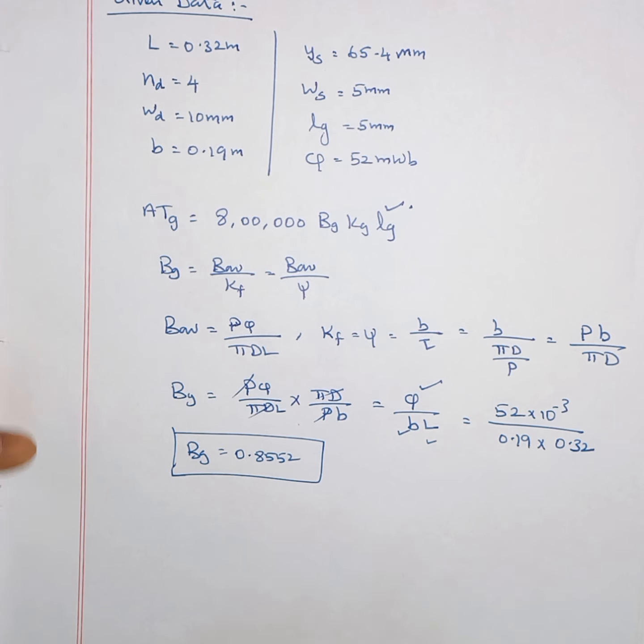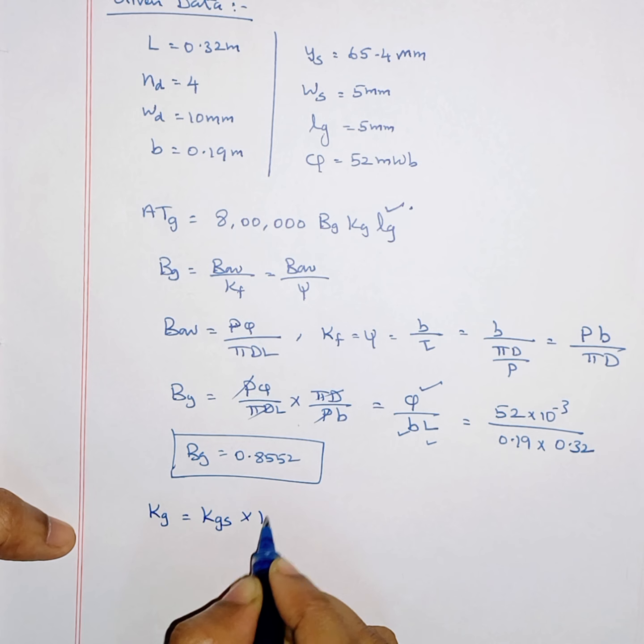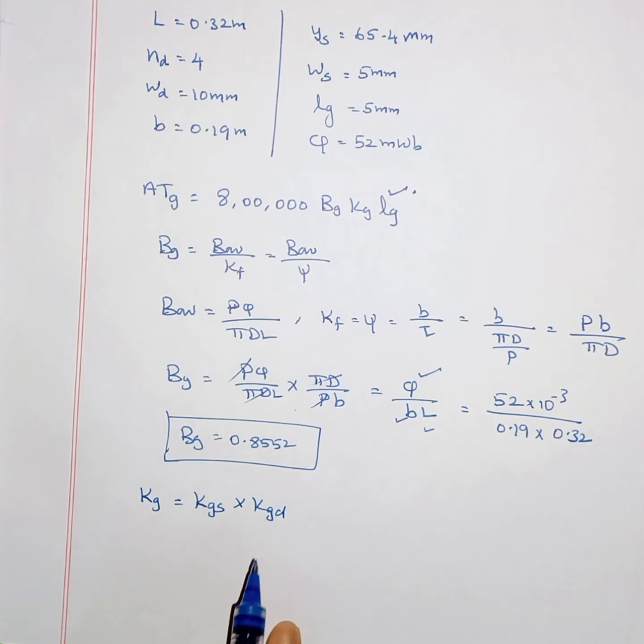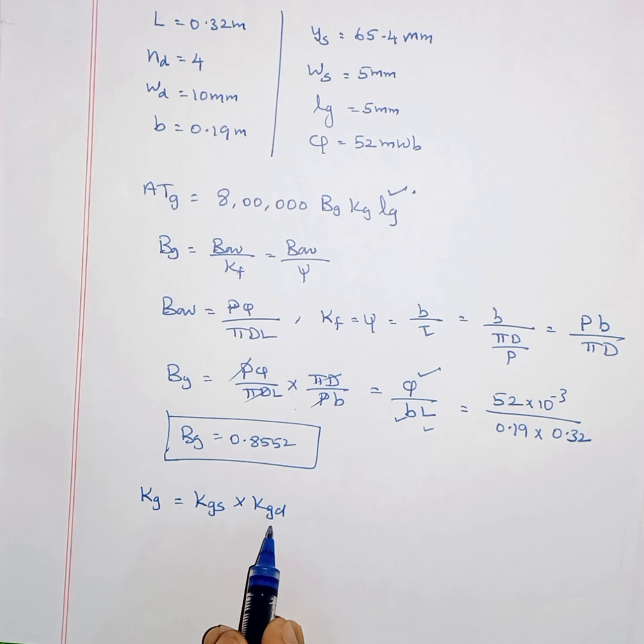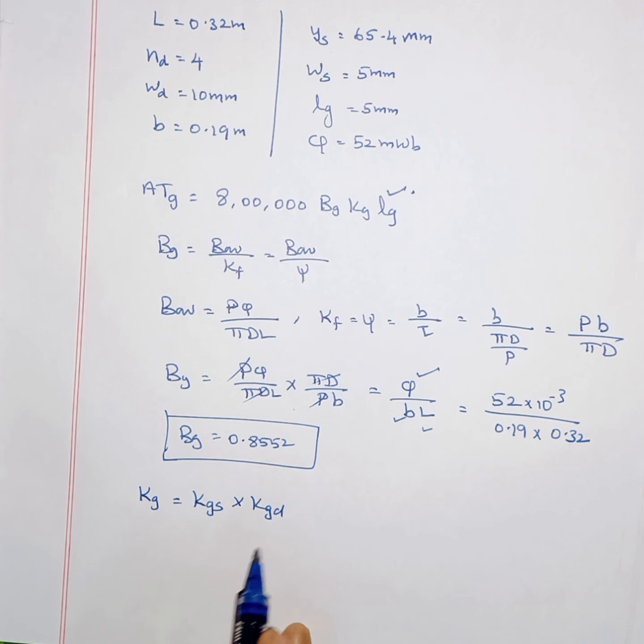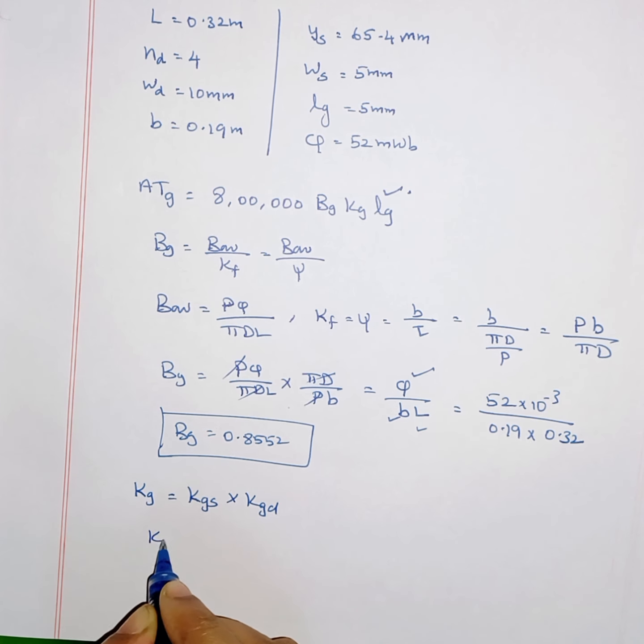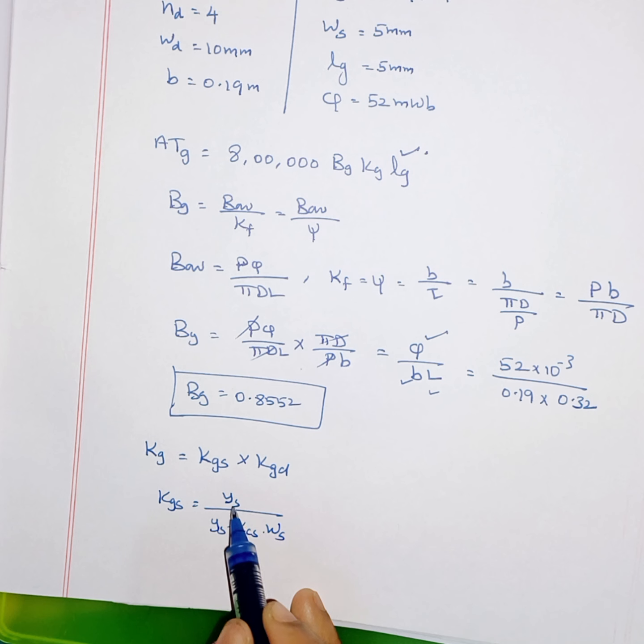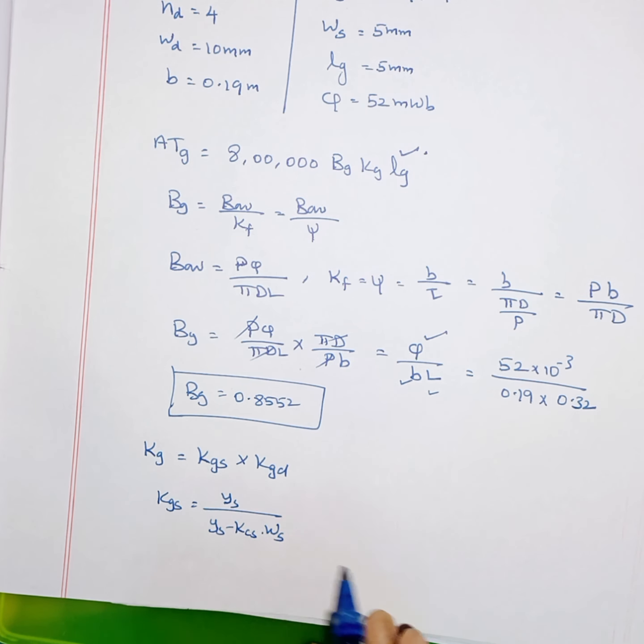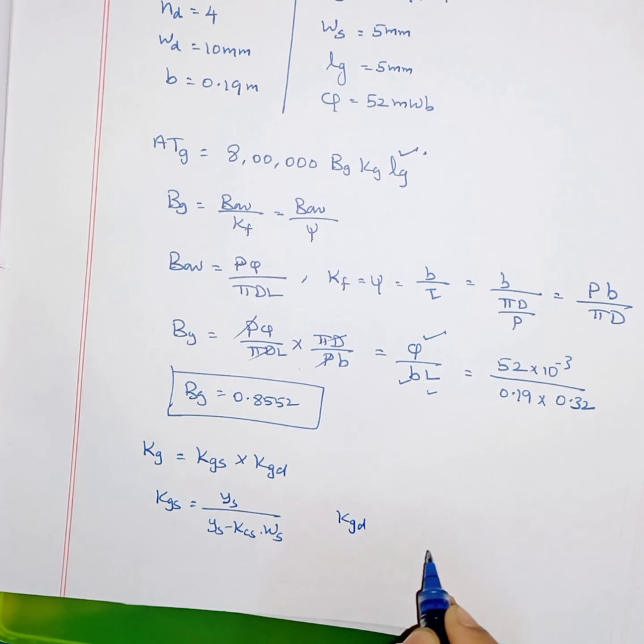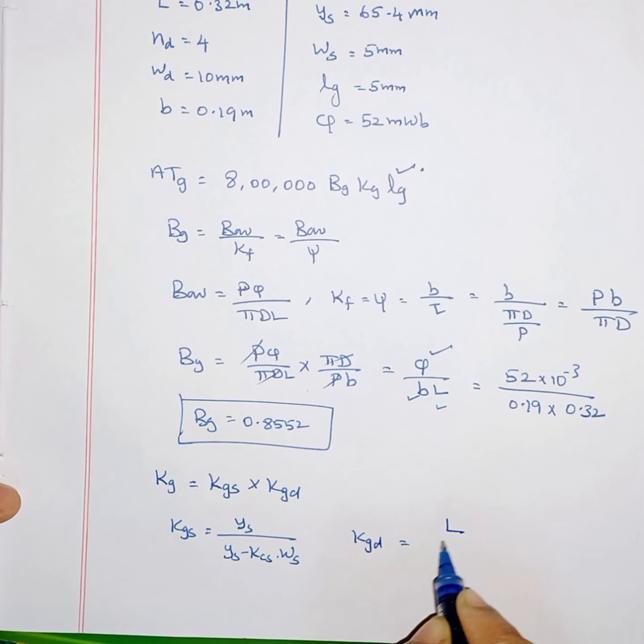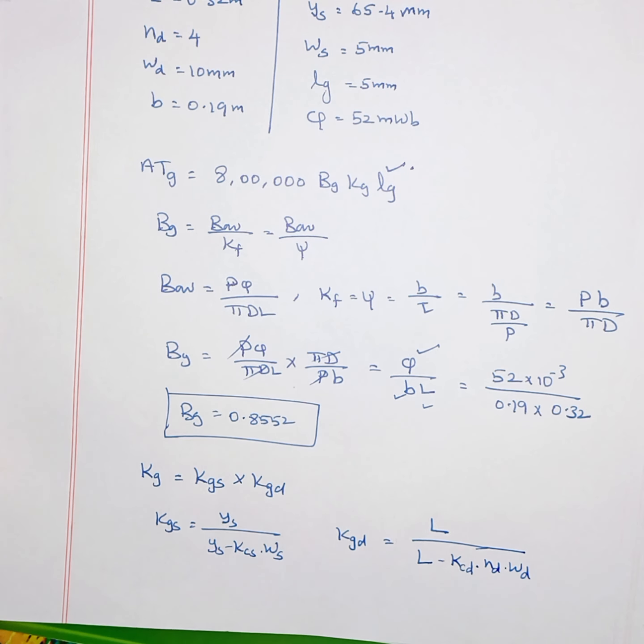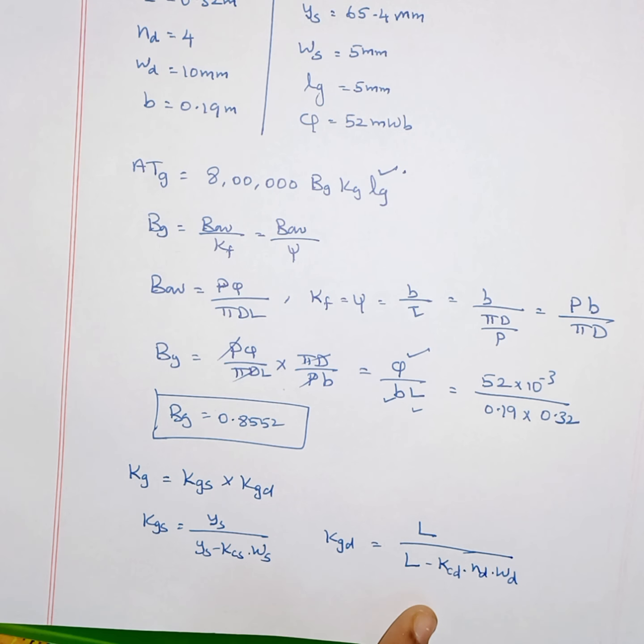Now we will find KG. As already explained, KG equals KGS times KGD — gap contraction factor for slot and gap contraction factor for duct. Since ducts are given here we must consider KGD also. KGS formula is YS divided by (YS minus KCS times WS), and KGD is L divided by (L minus KCD times ND times WD). We need to find KCS and KCD first.